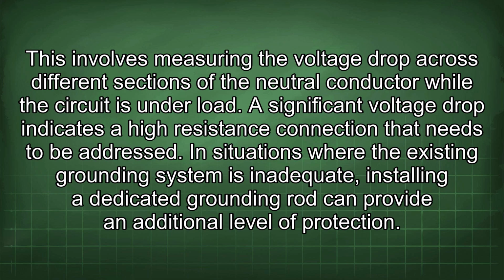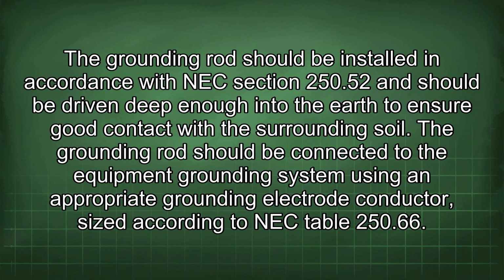In situations where the existing grounding system is inadequate, installing a dedicated grounding rod can provide an additional level of protection. The grounding rod should be installed in accordance with NEC Section 250.52 and should be driven deep enough into the earth to ensure good contact with the surrounding soil.